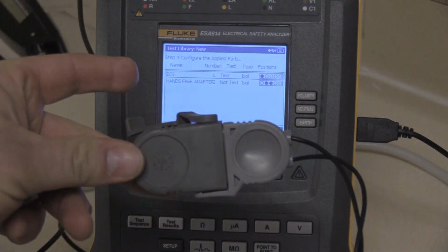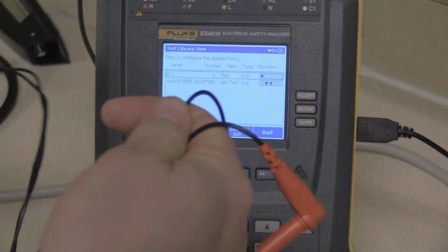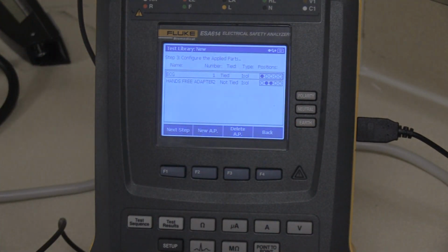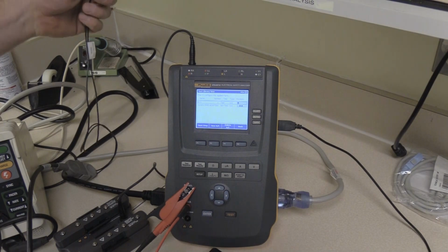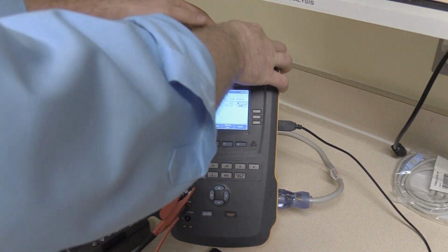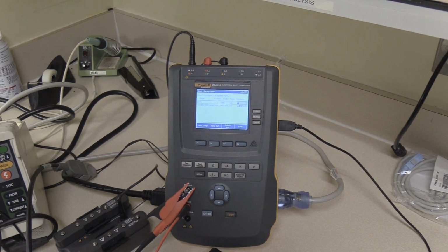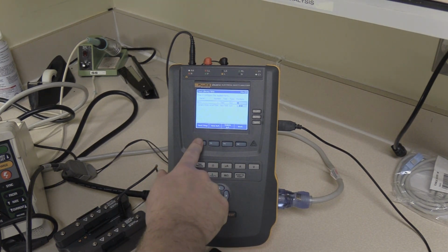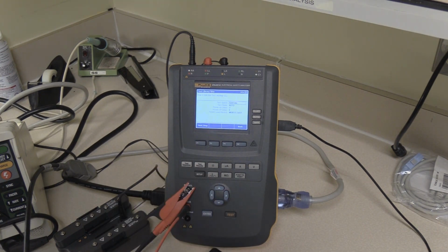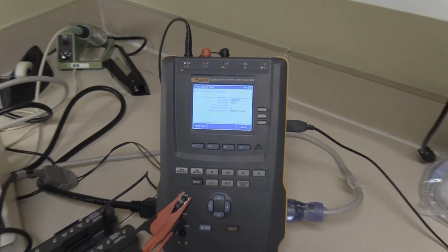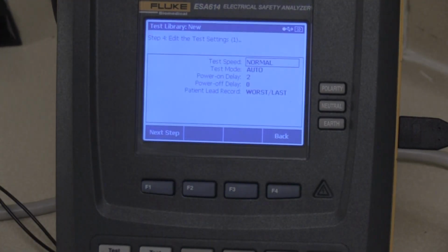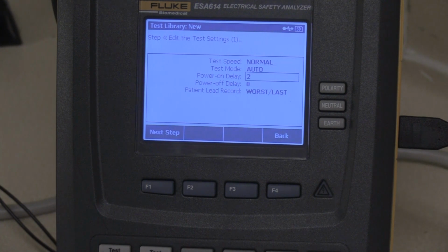Now we're going to connect the hands-free adapter to the defibrillator, and we have our 2 ports here, and we'll scroll back so you can see the top. We're going to connect those into the 2 corresponding ports on the top of the ESA614. So that's going to be the hands-free adapter, and we're going to hit next step, and normal speed, everything's good. We're going to go back and review the rest of the screens. Everything else here is good.